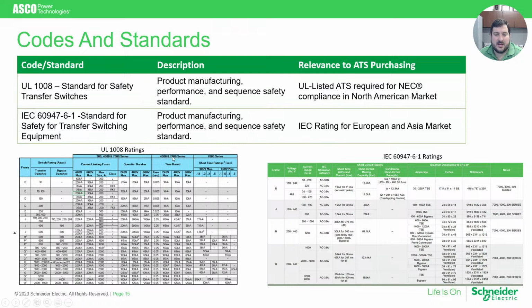As you can see at the bottom here, one of the most important things the standard controls, besides guaranteeing that the product is manufactured to a certain level of quality and performance, is around the short circuit ratings and WCR ratings, which we'll talk about in more detail later, which are different between the two standards. And that is due to the fact that the standards have different testing requirements, which could result in different levels of rating for the same product across both standards.